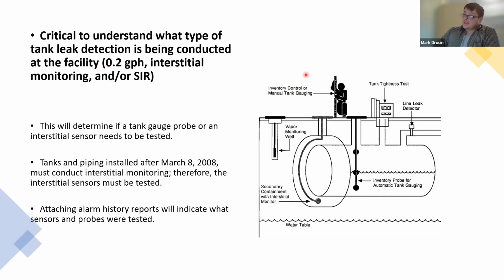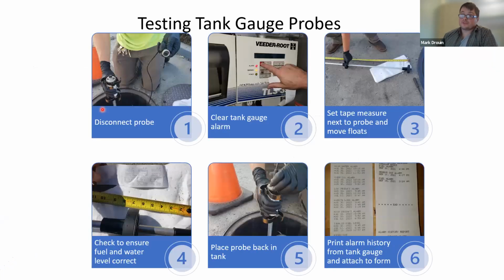Okay. So again, it's going to be critical to understand if you're testing your probe and a sensor. The next couple of slides are going to be talking about testing a probe and a sump sensor. Probes and sensors can be different. I was just out with an operator who was willing to help us with the form, and this is what we did. As an example, for this Veeder-Root system, if you follow the PEI method and the Veeder-Root method, this is a very quick summary. This isn't every step of the way. Please reference those manuals, but as an operator, if you're watching your tester, this is in general what you're going to want to see for their probes.